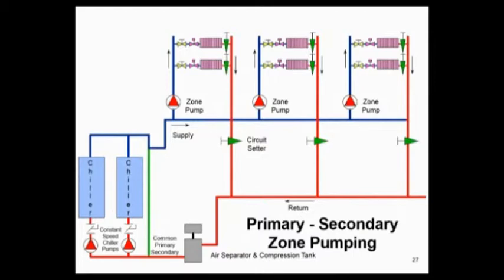Here's a zoned pump. I got rid of the primary pump and I've got an individual pump in each building pumping the distribution piping out, distribution piping back. This was called zone pumping or distributed pumping. If you go to ASHRAE book, you will see them in the journals and they're defined for you. I'm asking you, before you try to balance a building, to sit down and make this simple system sketch to know what the intent is of the design. Otherwise, there's no way you'll ever get this thing balanced properly.